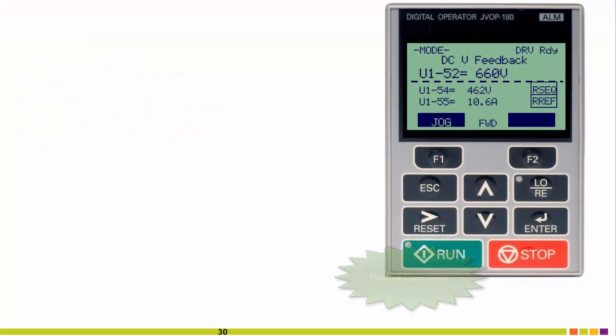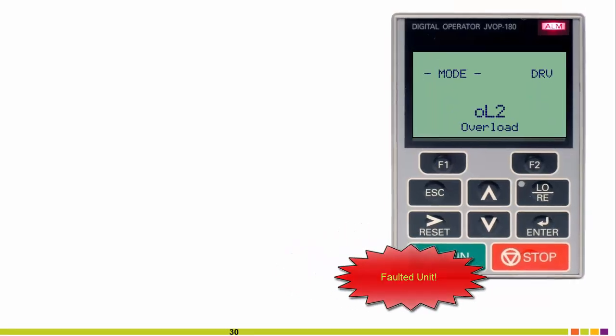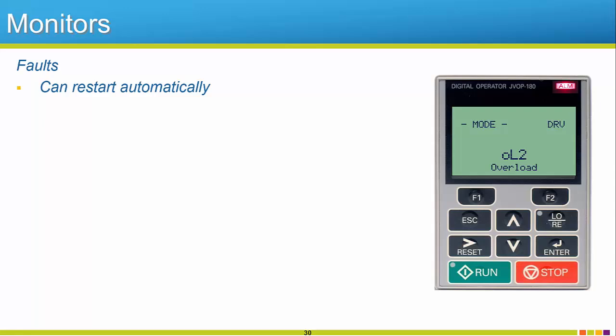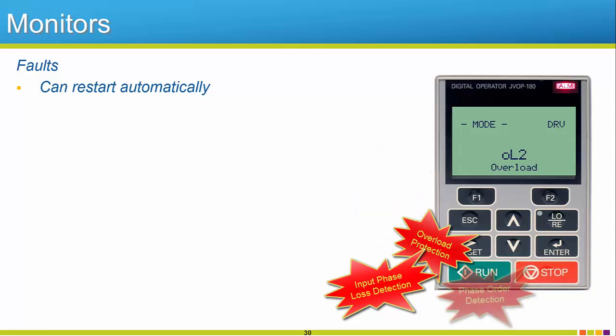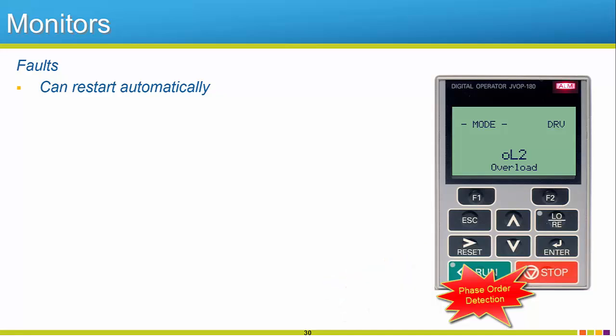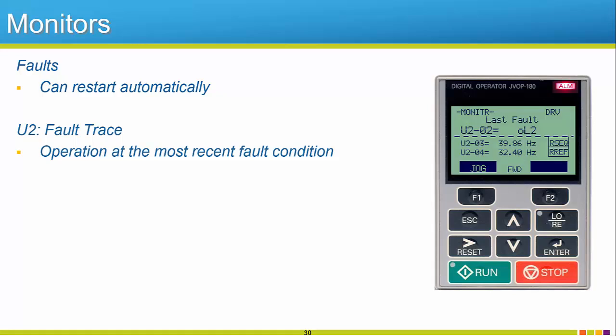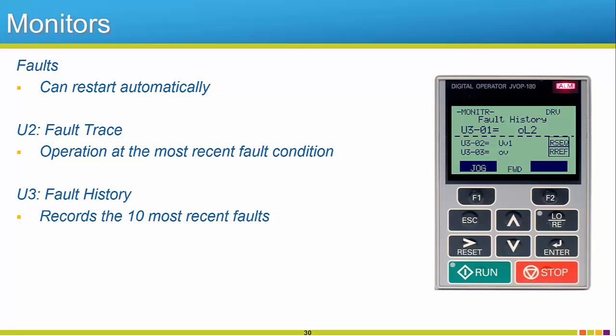If a fault were to ever occur on the R1000, we've got you covered. The unit can be set up to automatically restart on a fault if desired. There are also a number of faults ingrained into the R1000's programming to protect the unit and your application. To name a few, there is a power supply over voltage and also under voltage detection, over current protection, overload, input phase loss, and also phase order detection. There are also two monitor groups solely dedicated to helping the operator troubleshoot any fault. The U2 monitor group will list what occurred at the most recent fault. Think of it kind of like a snapshot that was taken during a fault to list all of the monitors you will need to make an analysis of what exactly happened. Secondly, the U3 group is your fault history group. This will list up to ten of the most recent faults. This is great for tracking previous faults and also checking for patterns.